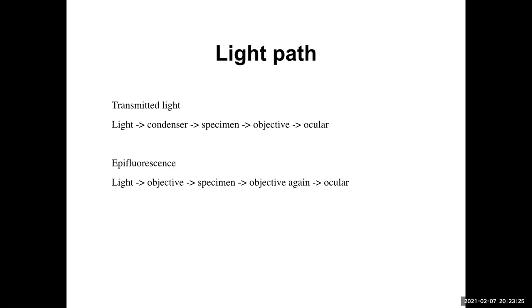Now, if we're talking about the light path of transmitted light — usually bright field of some sort, including phase and DIC — versus the light path of epifluorescence, also a reflected or incident light, the light path is different. For transmitted light, the light starts out at the bulb, goes through the condenser, through your specimen, to the objective, and then out to the ocular and cameras.